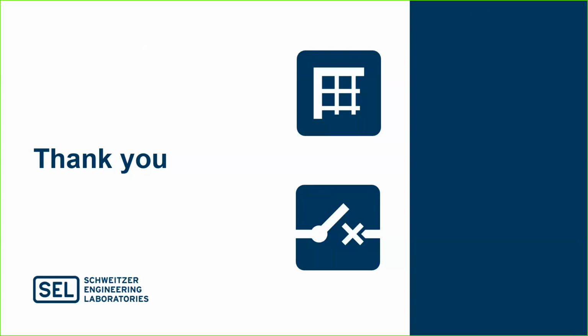Historically, when we have done FLISR on what's been the RTAC before Blueframe, there's been a 50-50 split between utilities that want to put this type of system right there next to SCADA or in a communications front end somewhere, or distribute it out into the substations. We designed FLISR partially feeder by feeder for that reason. So right now, FLISR needs to go on one Blueframe box. But a feature that we're working on this year is adding the ability to have those feeders talk to each other over an external network.